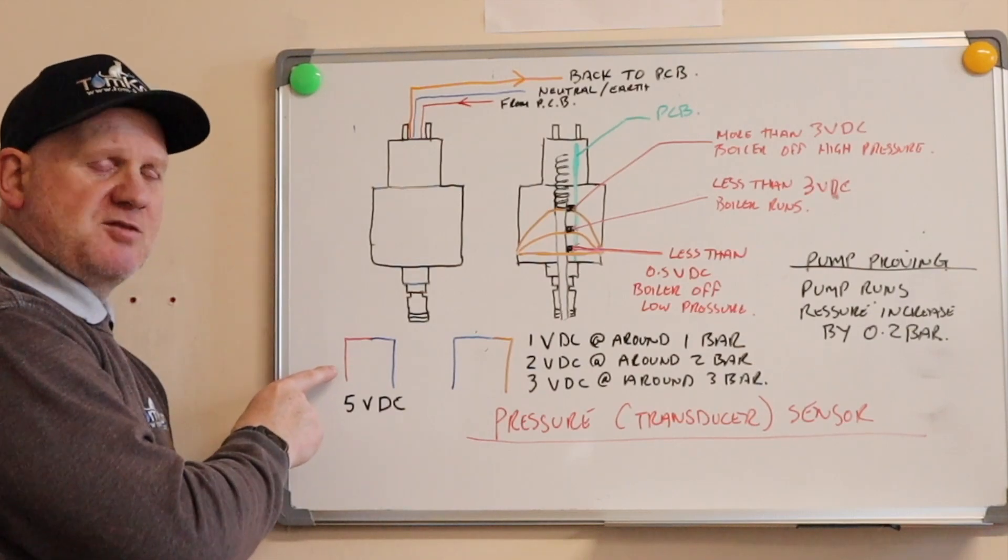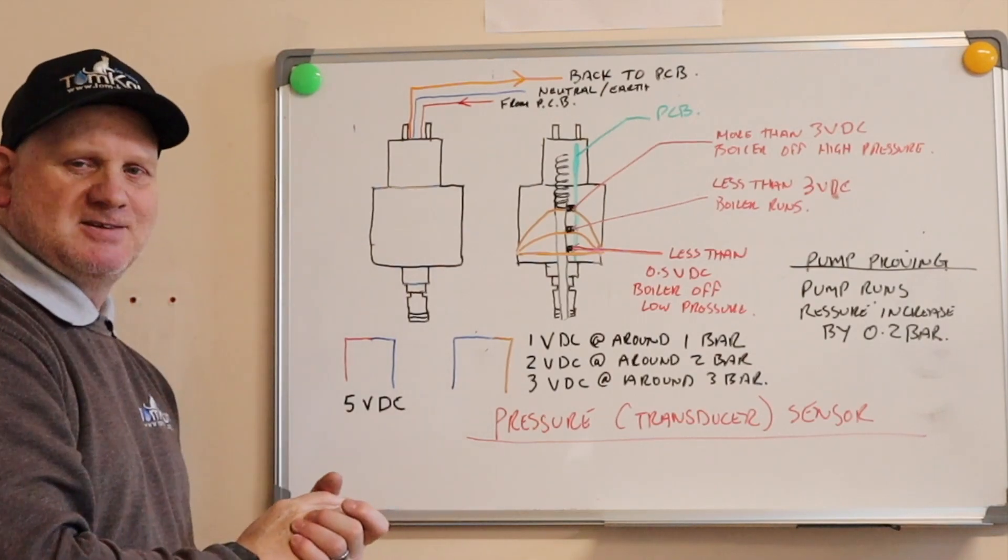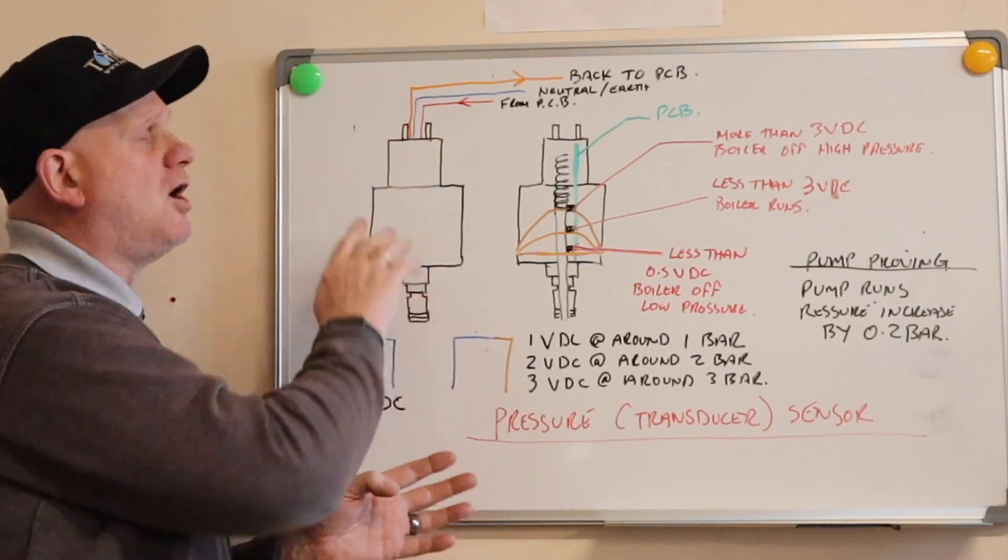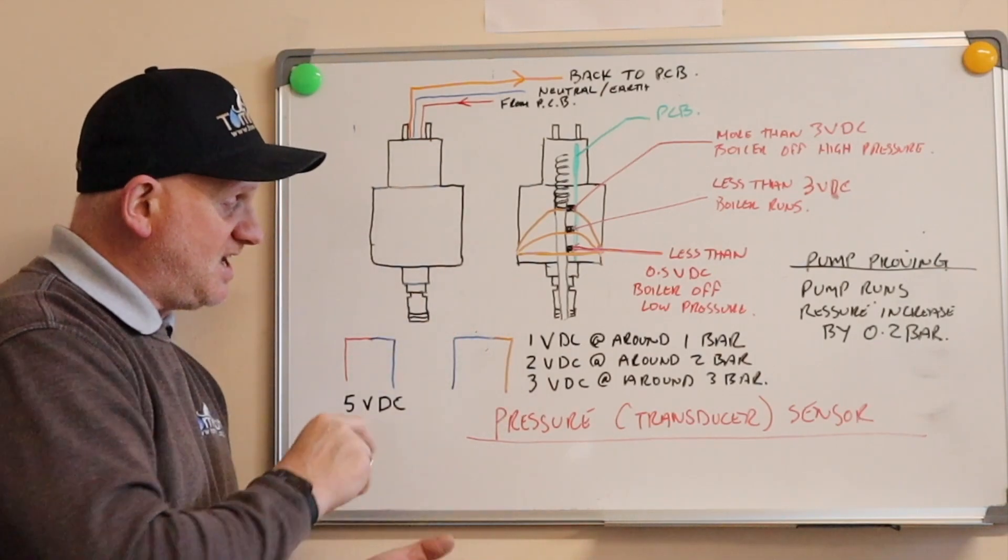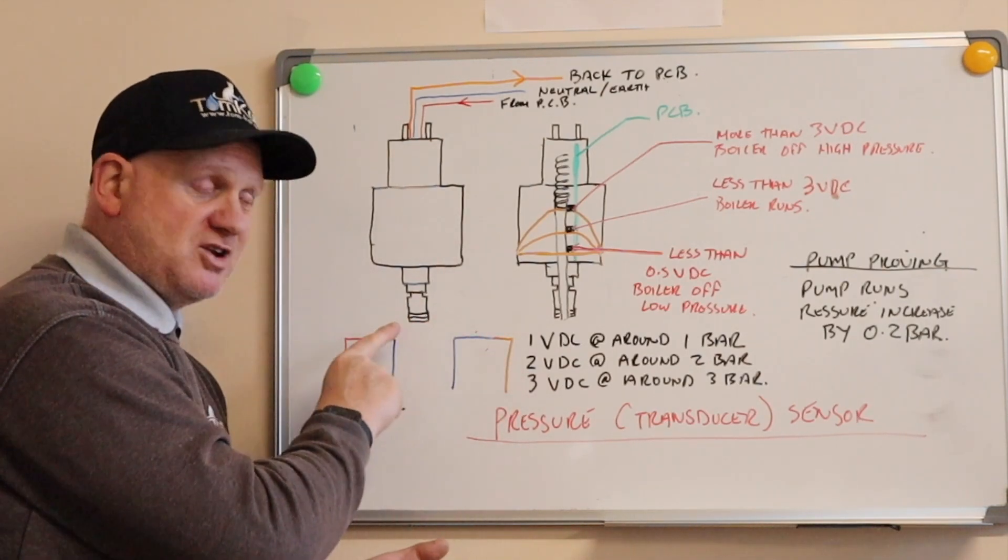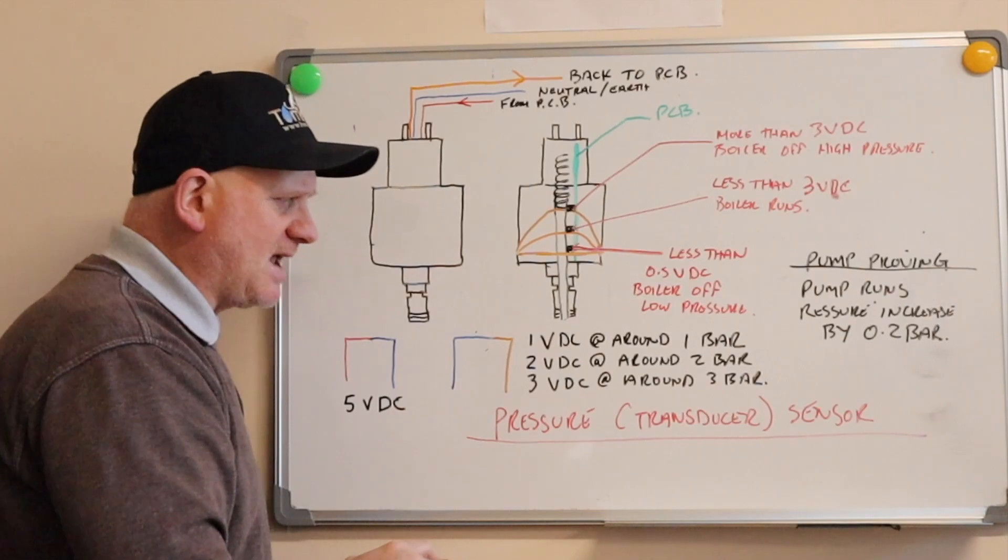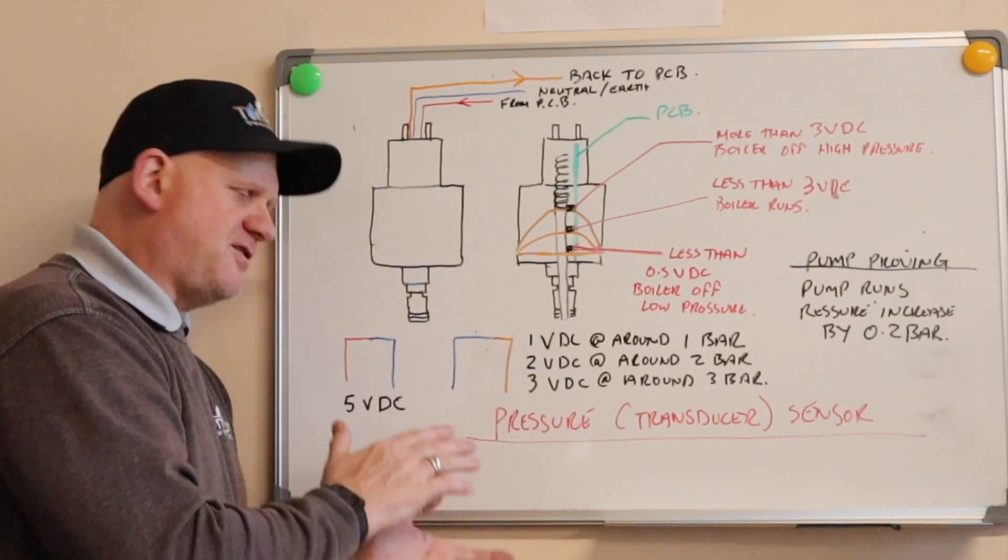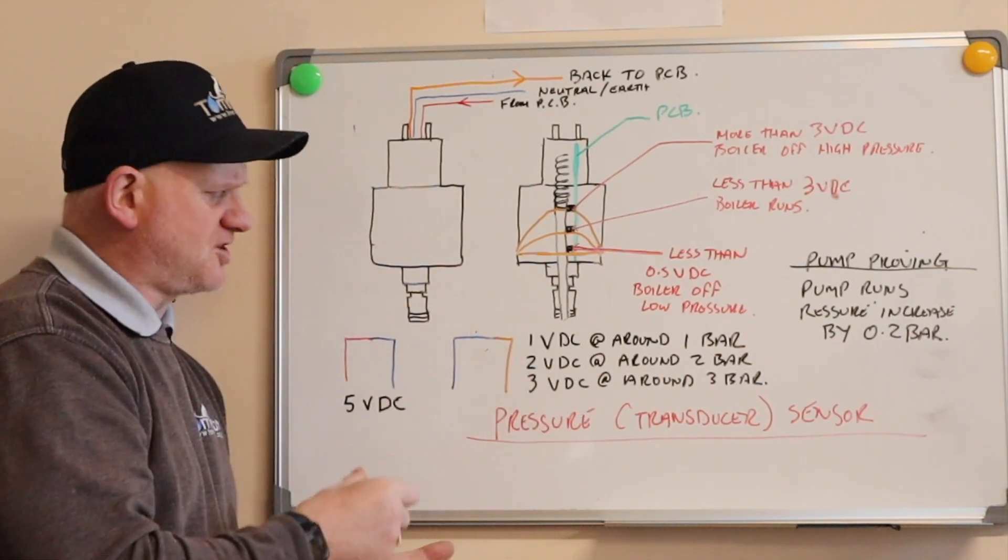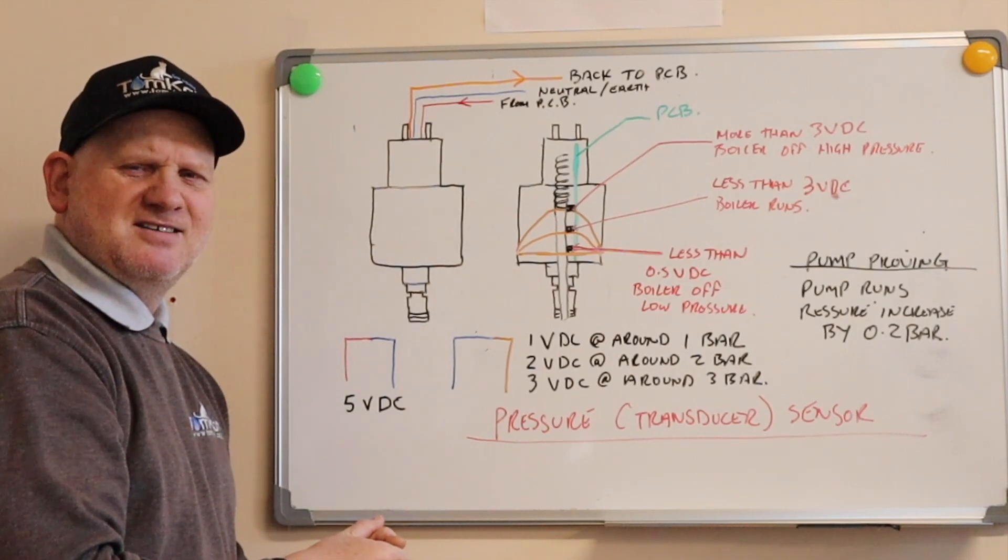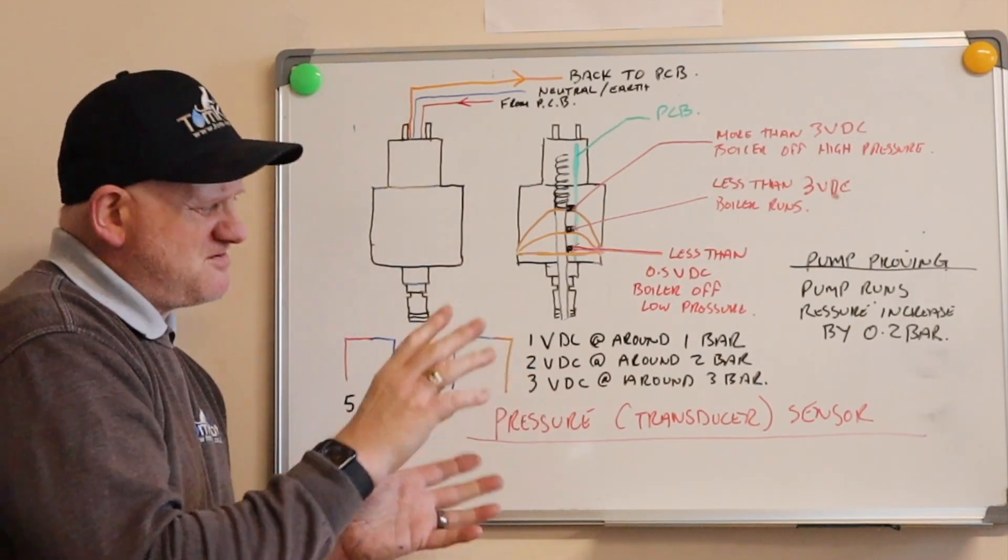If we checked between our red and blue wires we would get 5 volts DC. Depending on the pressure in the system will depend on what voltage DC we get back coming down the orange wire. If we had 1 volt DC coming back from the orange wire between the orange and blue, that would be around 1 bar. If we have 2 volts DC coming back, then it's around 2 bar. If we have 3 volts DC coming back, it would be around 3 bar. And if it got 5 volts DC coming back, then it's knackered. But that's a rough estimate and it's slightly different for different boilers.